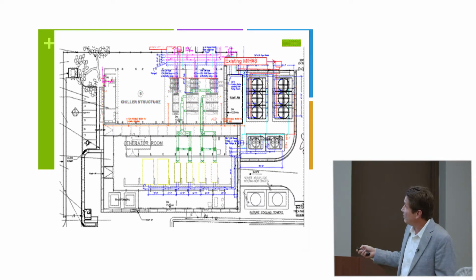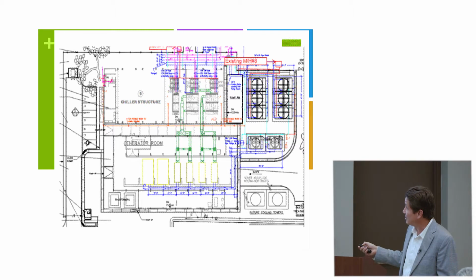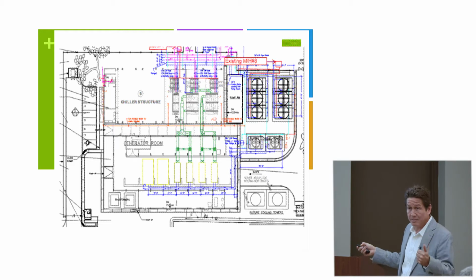Phase 1 involved using 2 exhaust chillers, direct fired and exhaust, multi-energy chillers that can run on LPG, diesel, waste, or exhaust. These are the exhaust ducts from the generators going into them. There's also a hot water chiller, since hot water from the generator radiators can be piped to it. So it's 2 800-ton absorption multi-energy chillers, direct fired or exhaust, and 1 800-ton hot water chiller. These are the cooling towers.